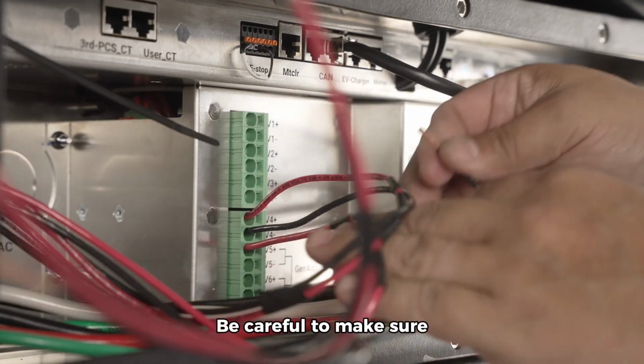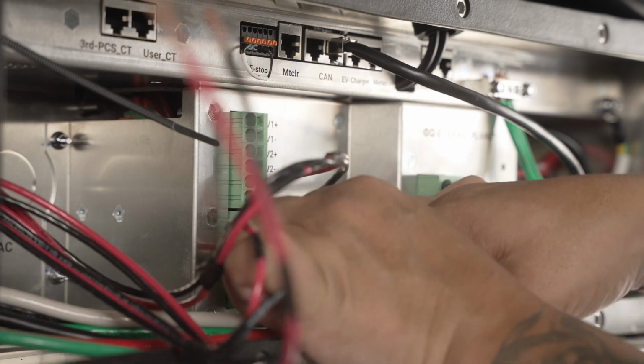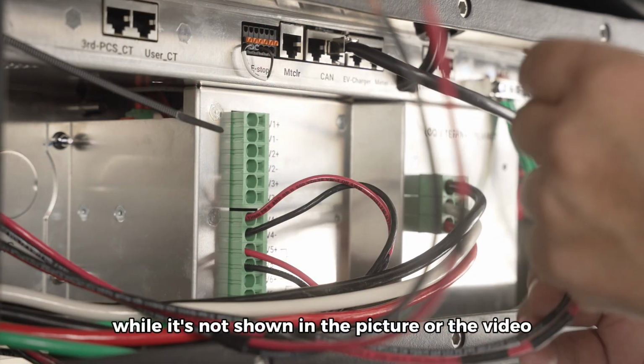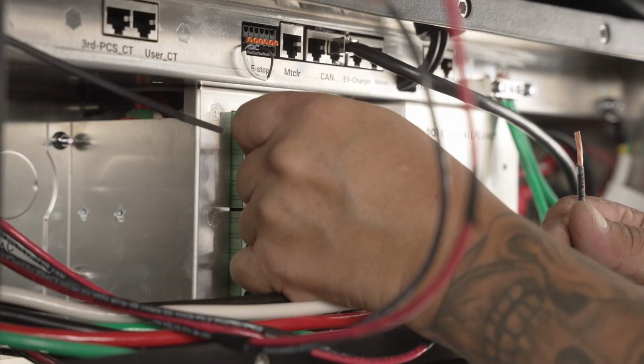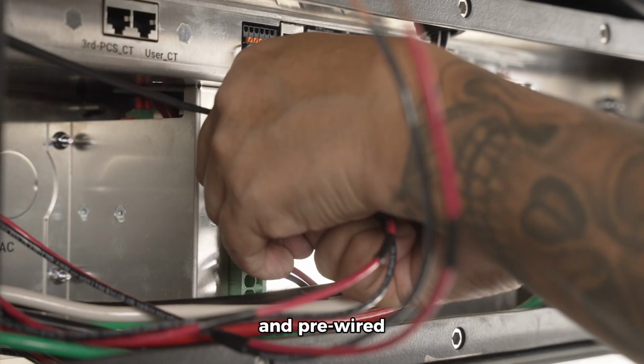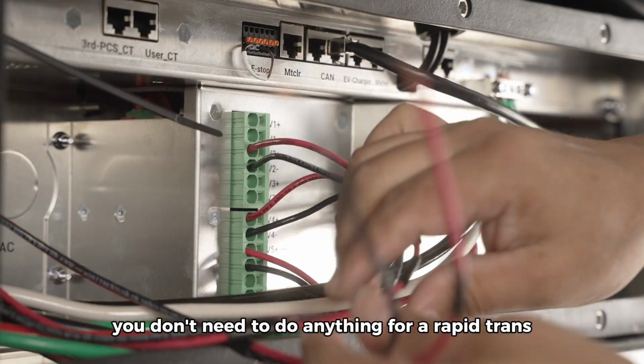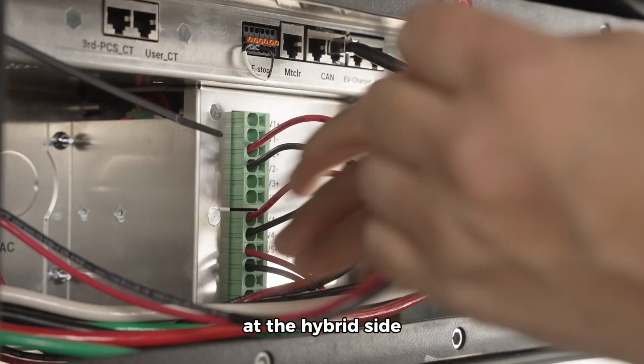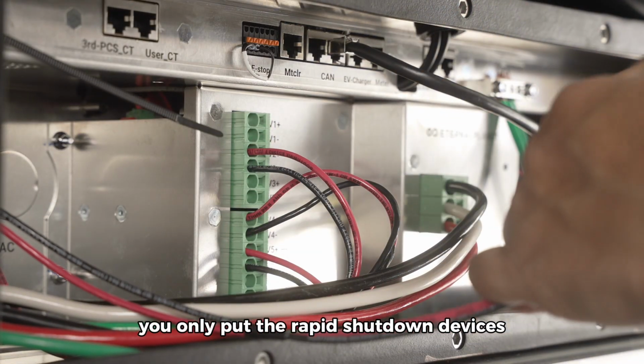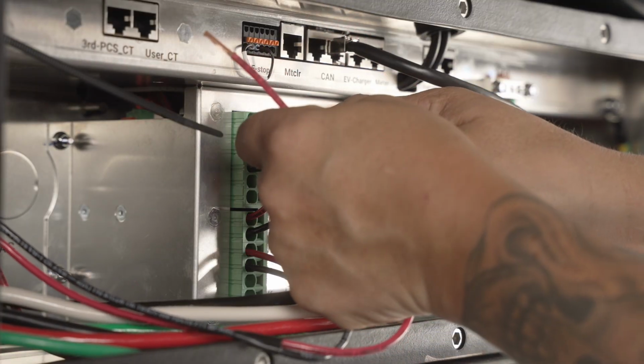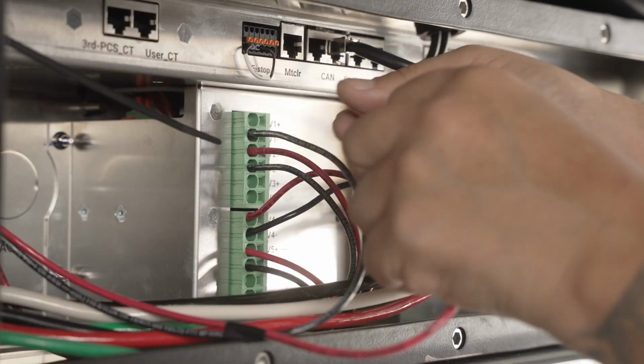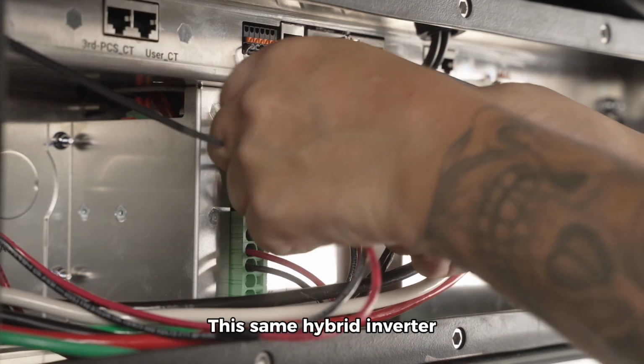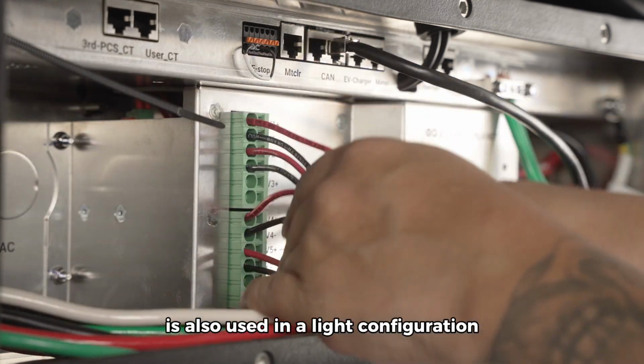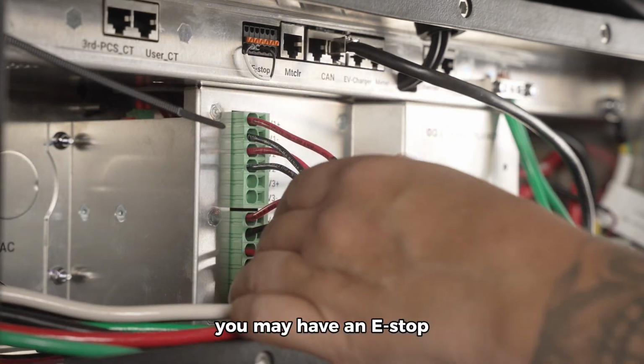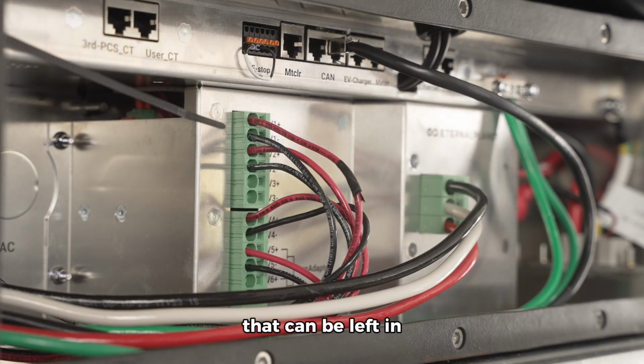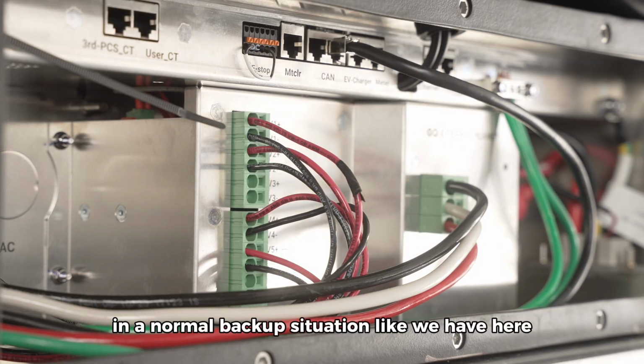Be careful to make sure you do not have stray wire strands as you terminate your PV strings. While it's not shown in the picture or the video, your rapid shutdown transmitter is pre-installed and pre-wired. You don't need to do anything for a rapid shutdown transmitter at the hybrid side. You only put the rapid shutdown devices on the PV panels themselves. This same hybrid inverter is also used in a light configuration. If you have a light configuration, you may have an e-stop. You can see there's an e-stop jumper that can be left in a normal backup situation like we have here.